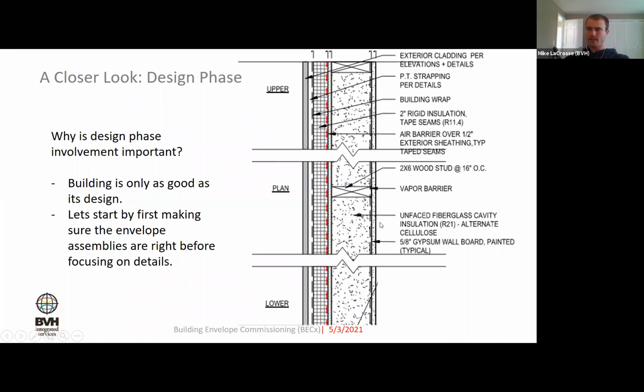So you could delete this layer and either increase the thickness here of your insulation to get that 50-50 balance, or decrease it on this side. Of course, you've got to make sure you're still meeting code minimum requirements. But in a nutshell, you could increase one side or decrease the other and eliminate this vapor barrier.